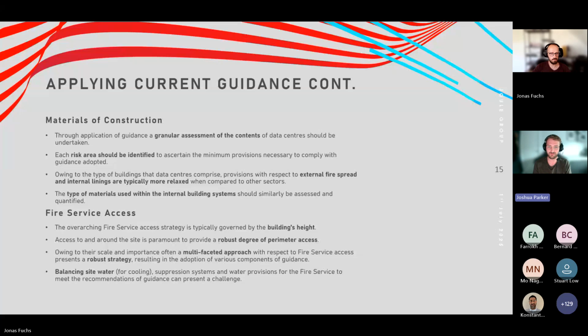For the internal building linings, for example, we typically rely on the minimum requirements as a minimum, but we do often see the need to apply either FM approved or UL tested materials that are specifically tailored to data centers. For instance, FM provide guidance on hot aisle and cold aisle containment materials, the selection of particular types of plastics, etc. And having that cognizance to know that information is available helps you to tailor a fire strategy specifically in this regard, away from the minimum requirements of the building regulations.